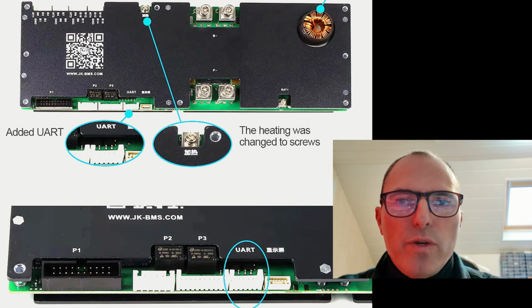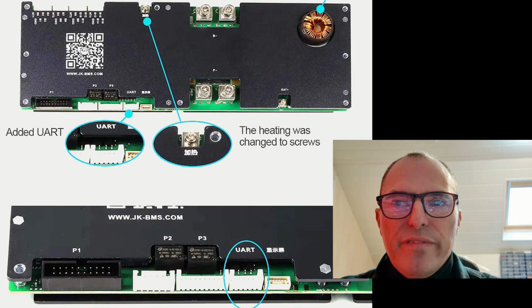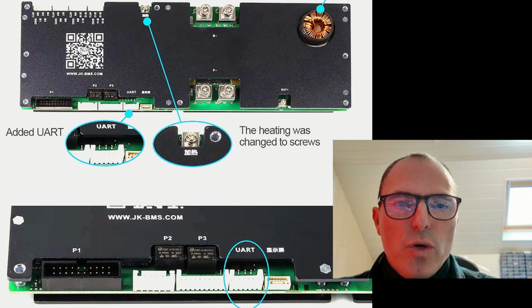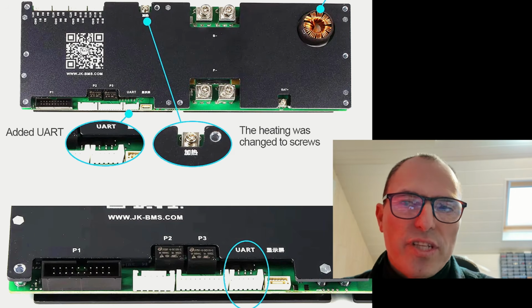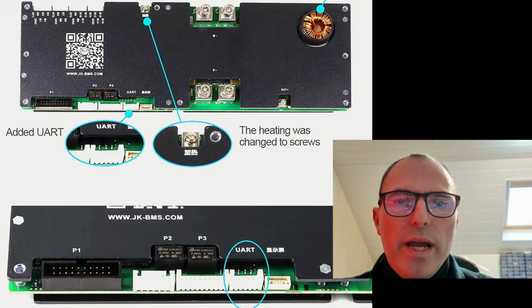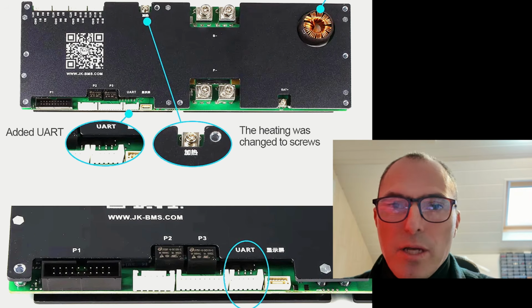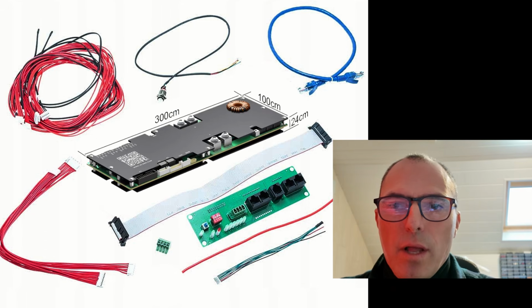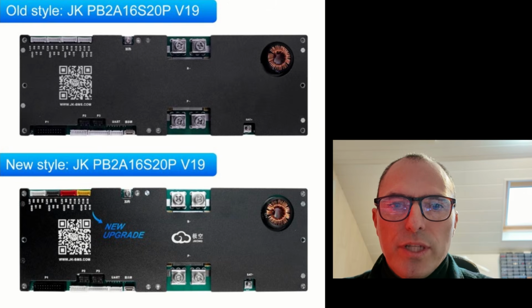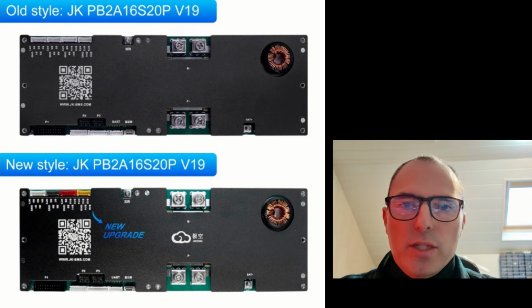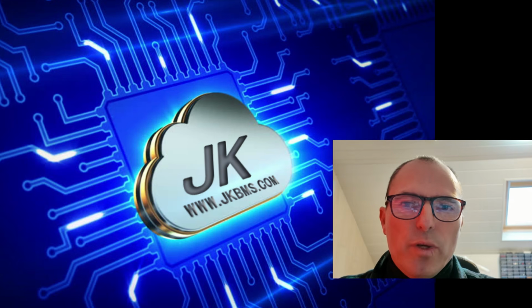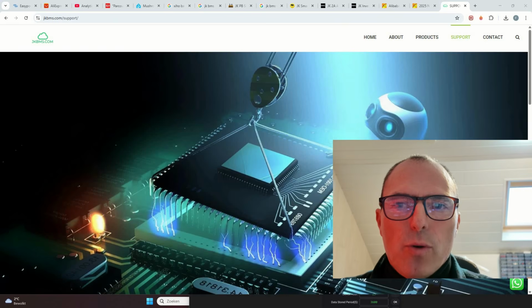Now, how to distinguish model V19 from 14 and 15? Well, V19 has no pre-mounted cable for the most positive voltage. There's no connector for the heat pad, just a single screw, and there's the UART connector to connect the display. The BMS comes in many flavors, several max amps. You have the 150 amp model, 200, 300. You have 1 amp balancing, 2 amp balancing. So check with your reseller to select the best option for you.